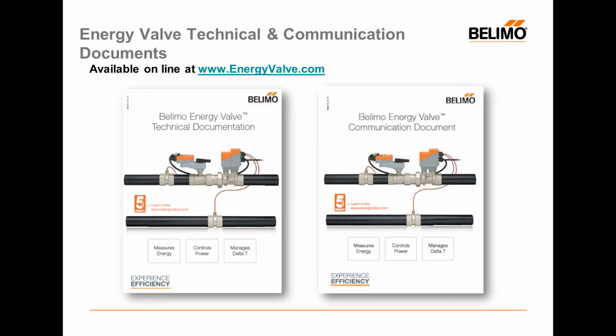Well, you would still have to download those files individually if you are tying directly into the Energy Valve's web server without the new data analysis tool. Once you have the new data analysis tool, you can use the tool to tie into the Energy Valve via its IP address, and it will do a batch download either directly into the data analysis tool, or it will store the files on the C drive of your computer. So with the new tool, you will not have to select them individually, and it should save you a whole bunch of time.